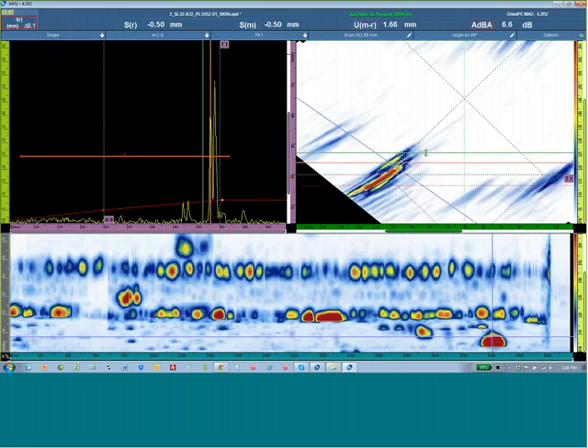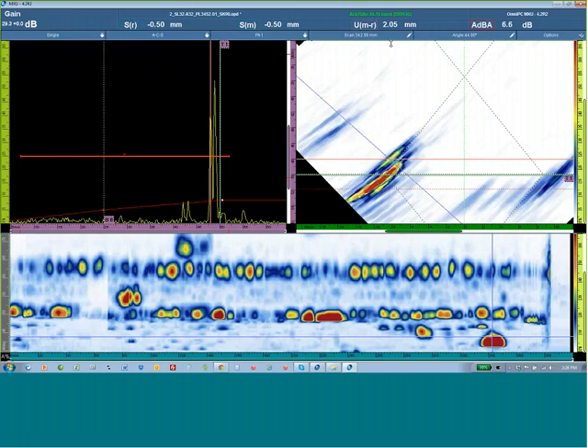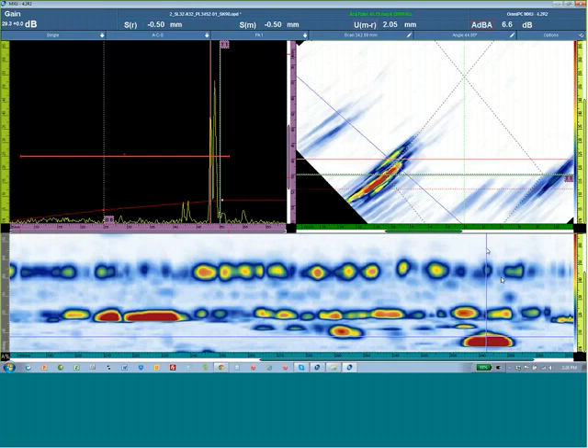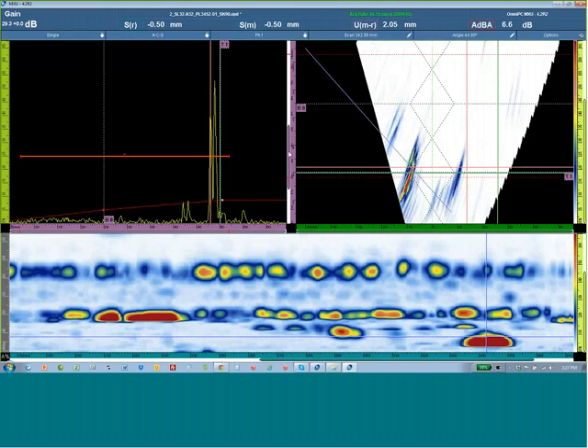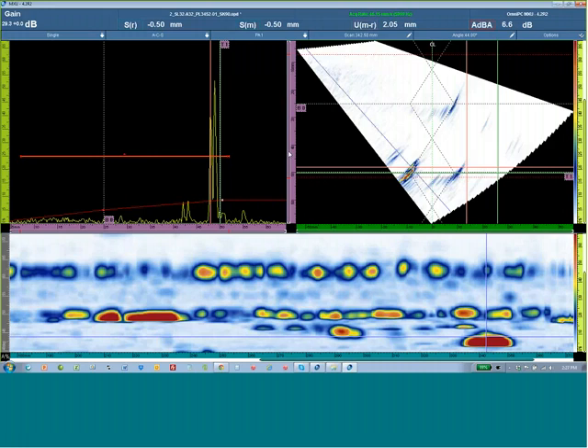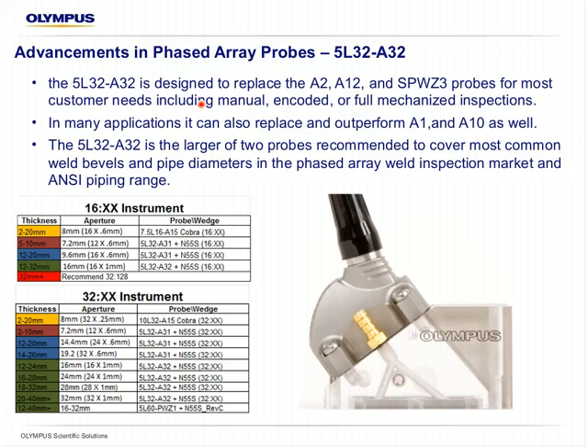We'll place another cursor on the full skip to the top, and we have a 2 millimeter through wall toe crack on the full skip at about 50 millimeters in true depth, or the full skip of a 25 millimeter weld. Very typical, and again, a 1 millimeter pitch, large aperture probe for long metal paths and thicker components in the range of 25 or 40 millimeters. The large pitch probe is going to help us greatly over a 0.5 or 0.6 millimeter pitch probe, whether using a 32 or 16 pulser instrument.